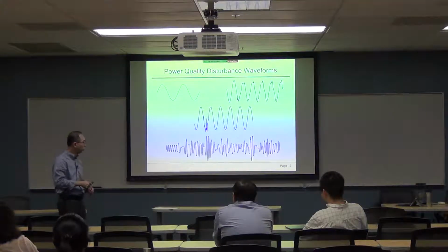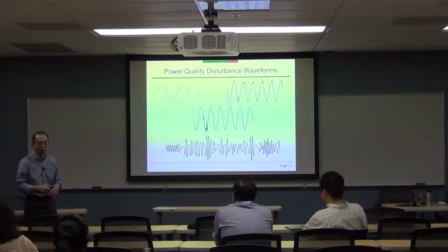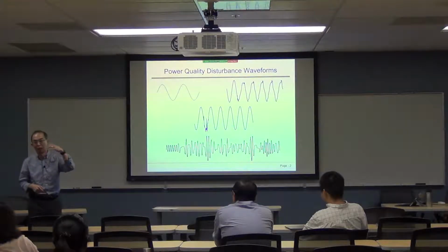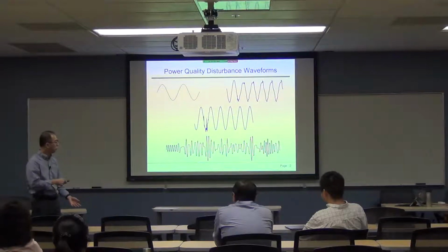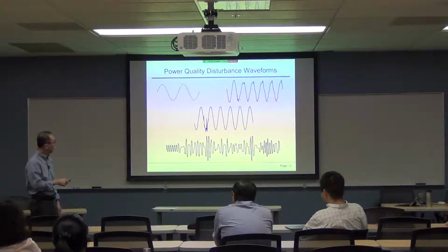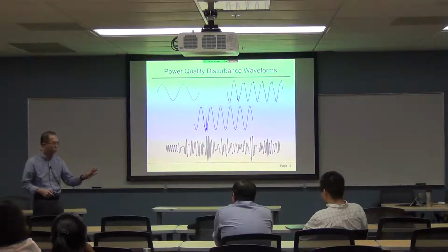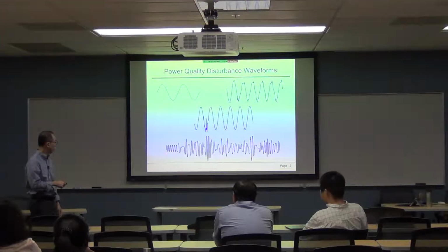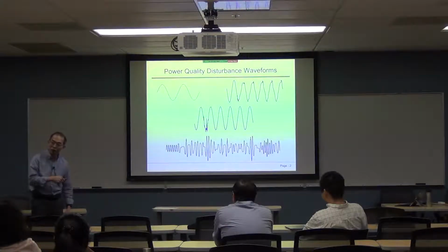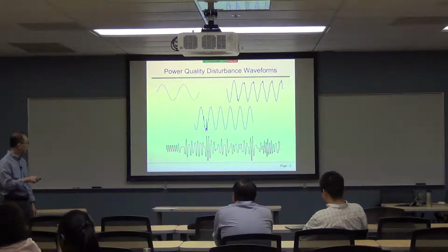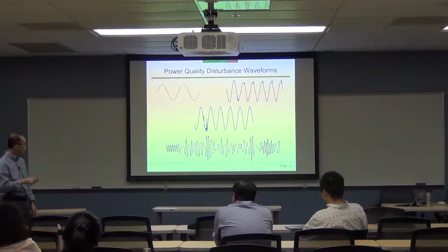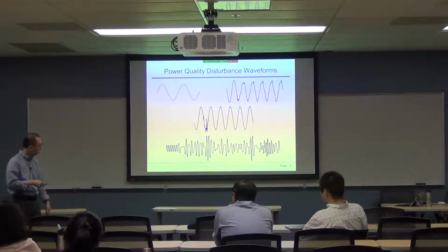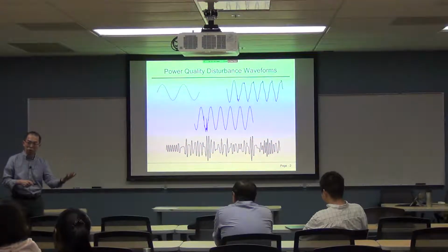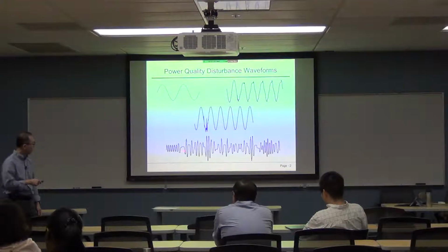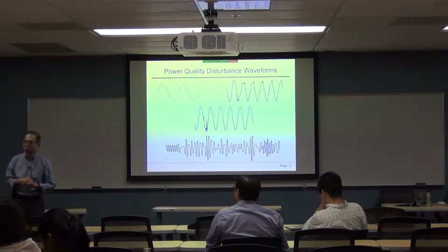This has to do with a capacitor being taken out of line, out of service, but then it restrikes. A capacitor de-energizing is supposed to be very smooth, and you should not see much transients. But in this one, the first few cycles of the waveform are smooth and normal, but then, due to some system conditions, it goes into what we call dynamic overvoltage.